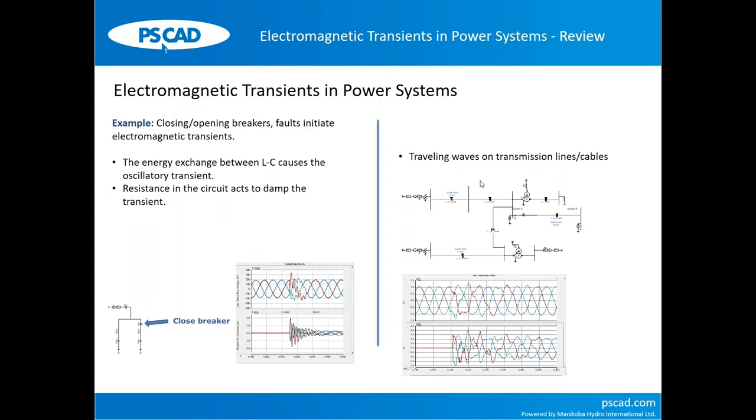The other thing that could happen is when you have transmission lines, when you close the breaker to energize a line, or when you open a breaker, or if there is a fault on a line, traveling waves get initiated. And these traveling waves, again, can give rise to transient voltages at the ends of the line or along the line. What we are interested in is the voltage that appears at the breaker, which is the voltage at the end of the line.